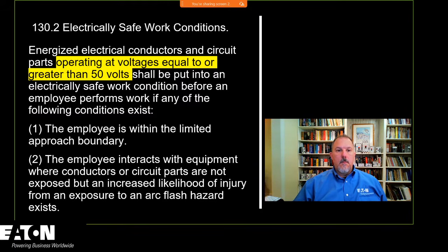We tell you that if you're below 50 volts, you have to take a look at the capacity of the source and any overcurrent protective devices, if any, and you have to make a determination that there is not a risk of an arc flash injury. So the best example there is we've all done something with a car battery and we made a mistake and we created an arc flash and we jumped 2 feet in the air and we were permanently scarred and our clothes were on fire. No, that didn't happen. But what happened was it scared the heck out of us. And when we went back into that automotive 12-volt battery, we were a whole lot more careful.